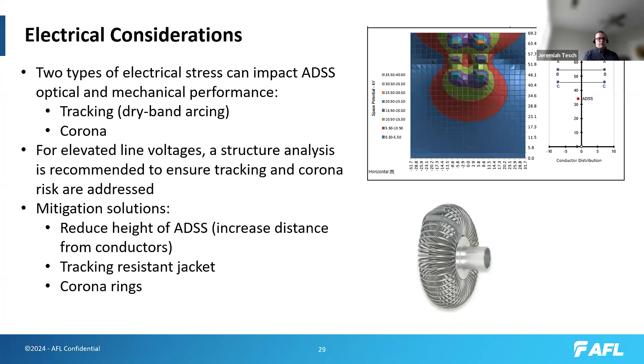And we can offer solutions such as simply reducing the height of the ADSS, which obviously has limitations sometimes. You can only go down so far, but that's often an easy way to reduce the risk to the cable. And then tracking resistant jacket material provides a little bit more protection against that tracking effect. And then of course, corona rings.